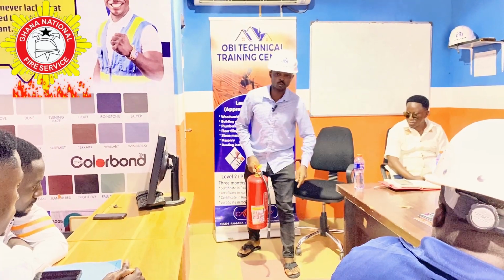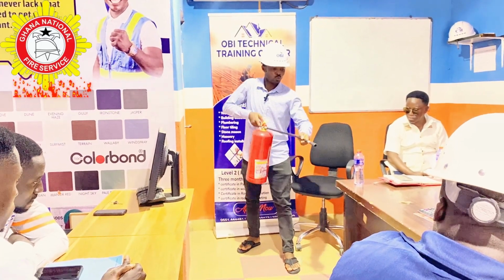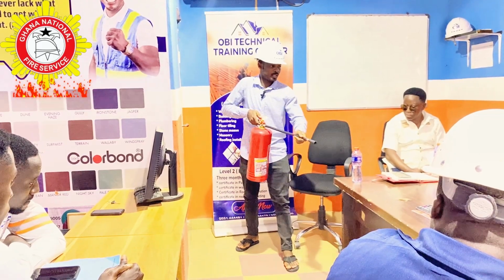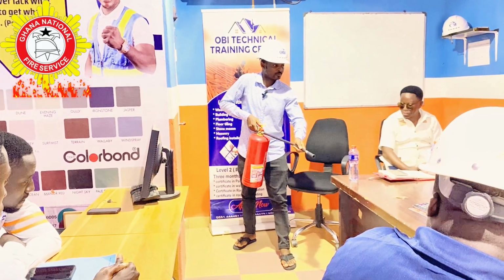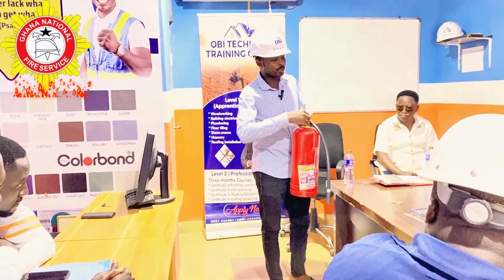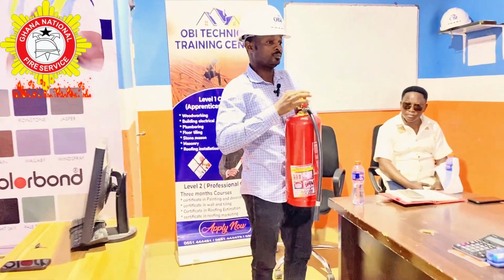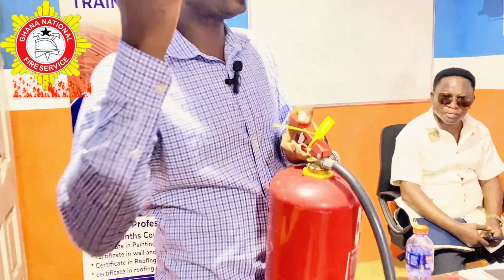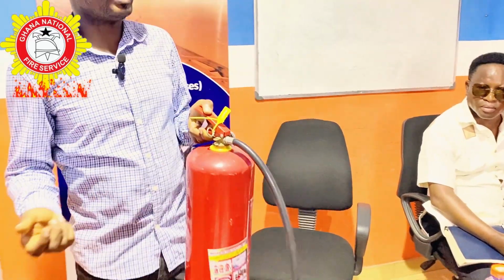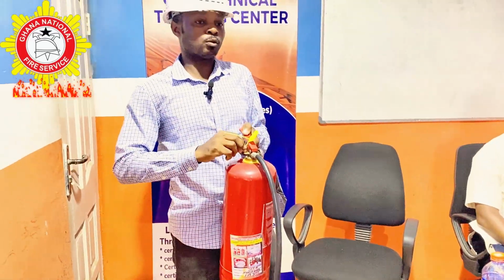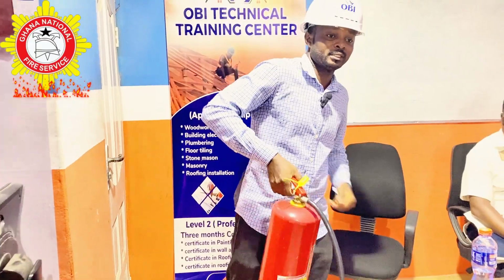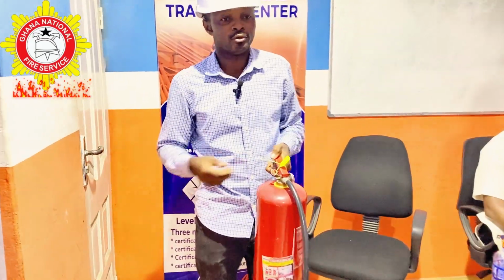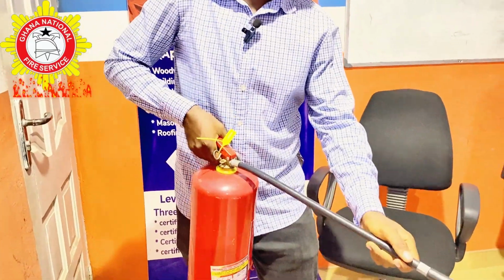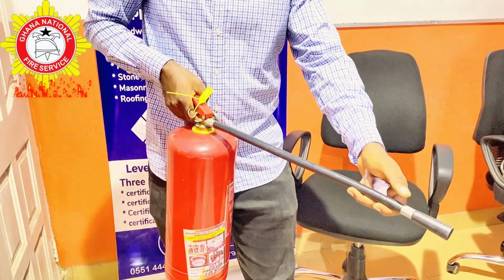So the best thing is to stand this way, hold it, and aim at the seat of the fire. Then you squeeze it. But before then, you take off this seal. You tear it off. You pull your safety pin. This is the pin that is not allowing you to press it. So the moment you pull it off and hold this way, you are good to go.